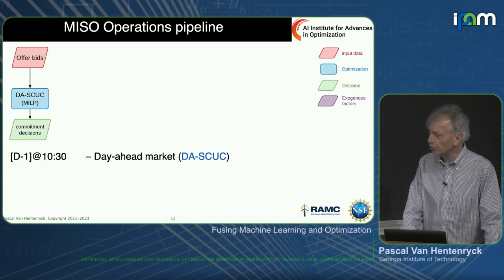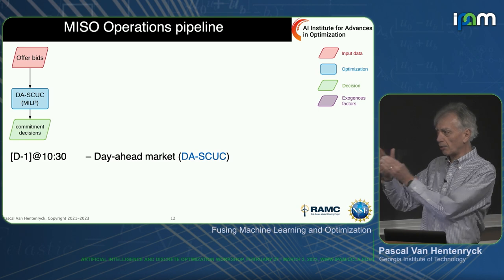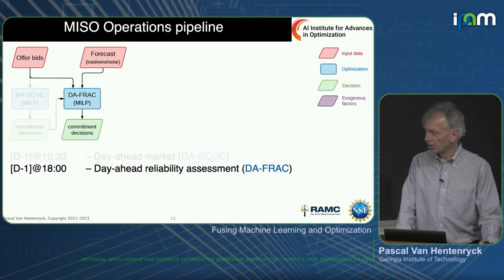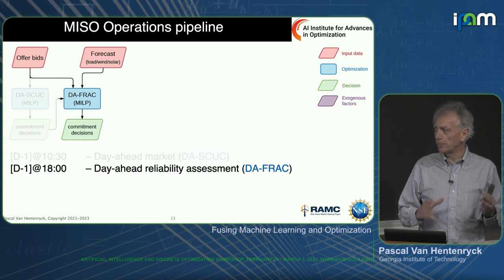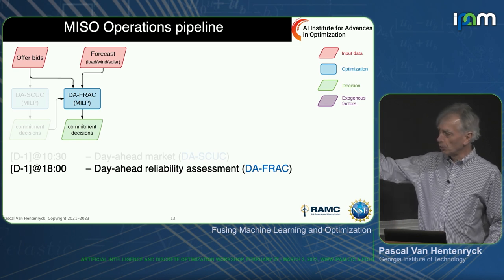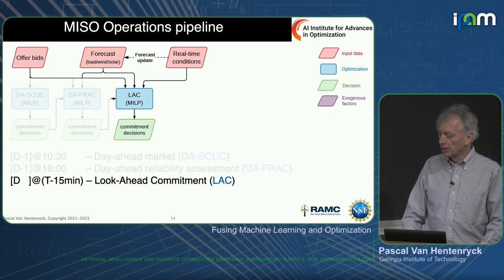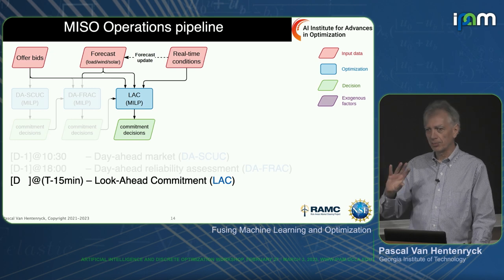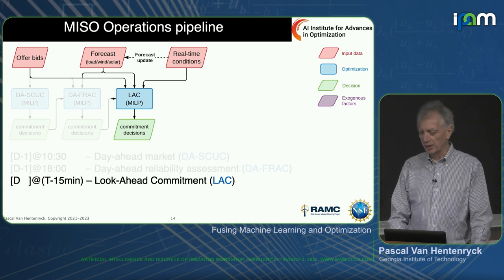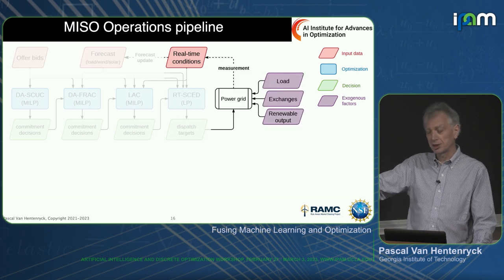This is a crash course on how systems in the U.S. work. The day before, around 10:30, every generator and load submits bids. You have the security-constrained unit commitment, which decides which generators are committed for the next 24 hours. About six to seven hours later, you have the reliability commitment, which uses forecasts in addition to bids to ensure reliability. Then every 15 minutes you have another reliability commitment for fast-starting generators, and finally the real-time market is executed every five minutes.